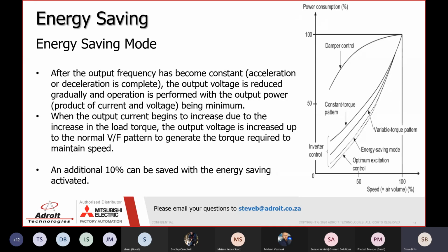So that is the basic principle of the energy saving. We have two energy saving modes in our VFDs. One is called the energy saving mode, and that one covers the following principle. After the output frequency has become constant, which means acceleration or deceleration is complete, the output voltage is reduced gradually and operation is performed with the output power being minimum.